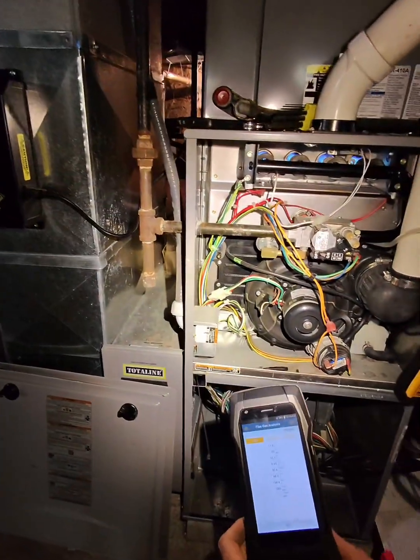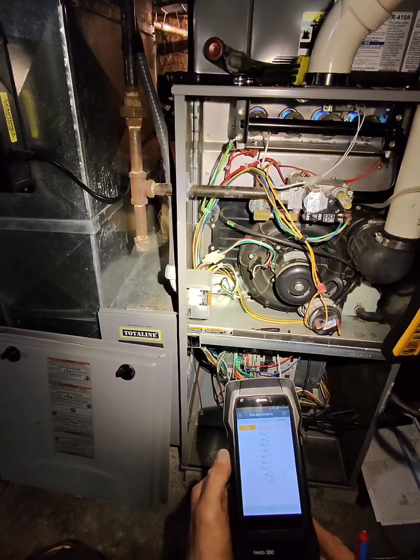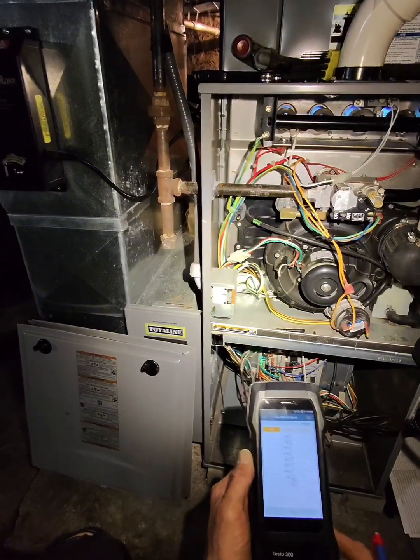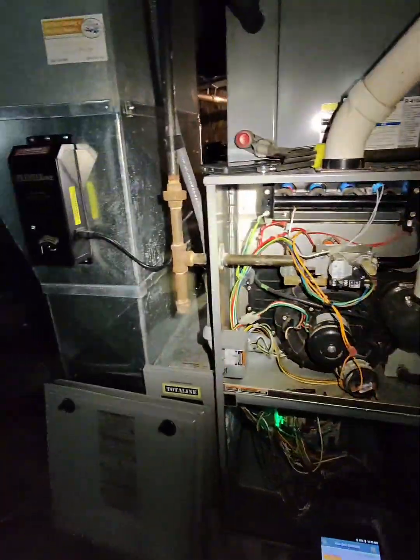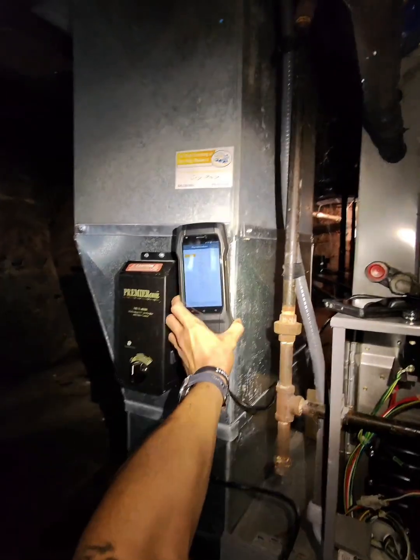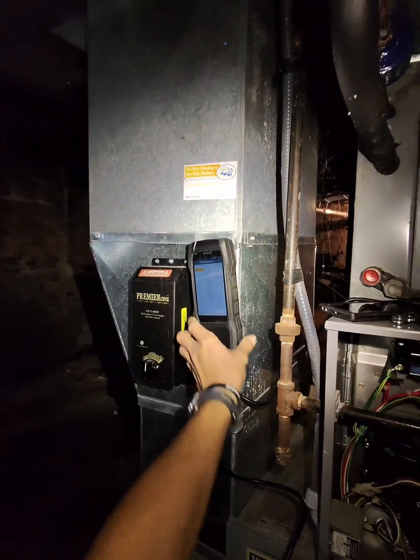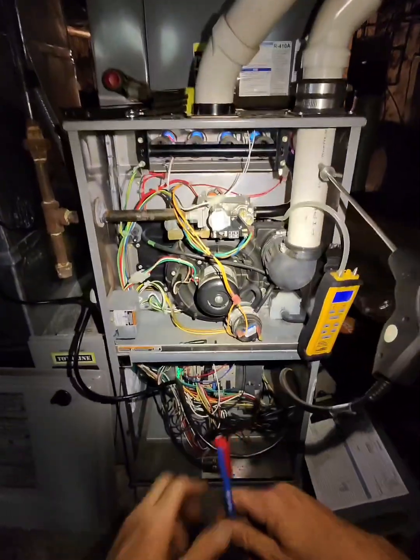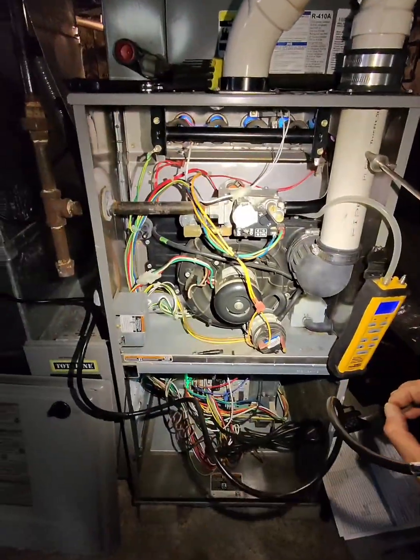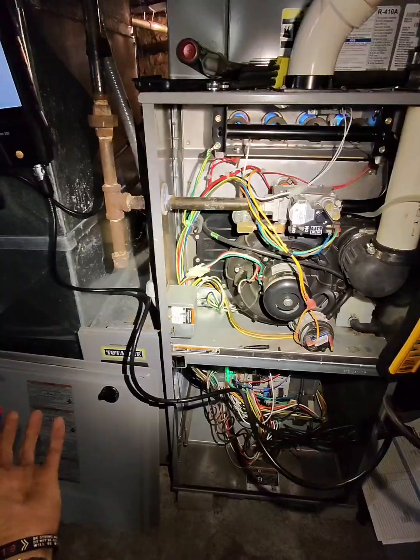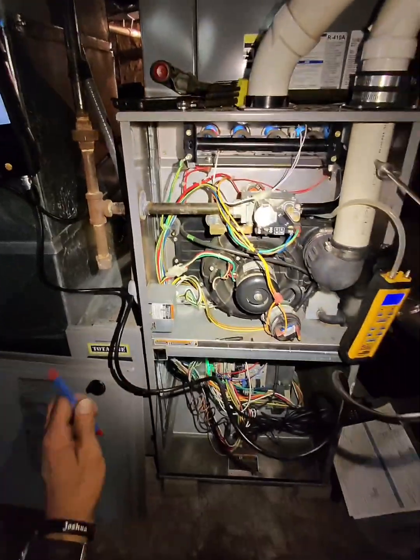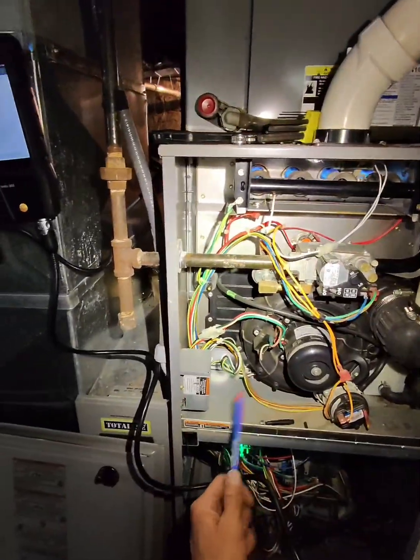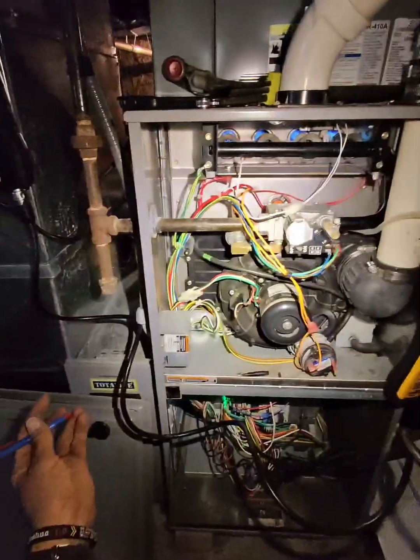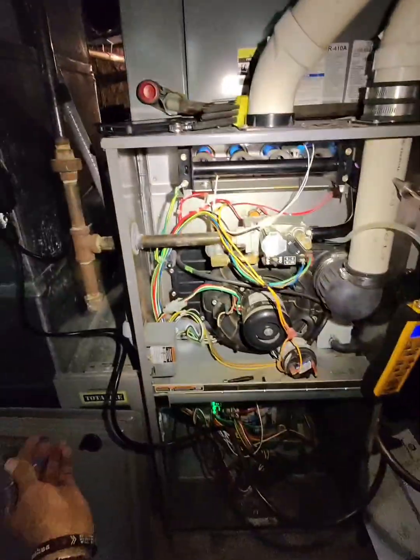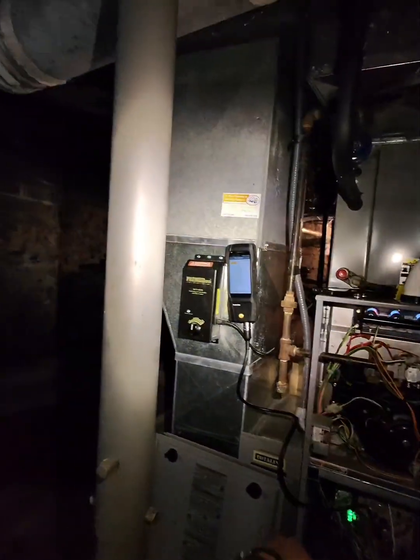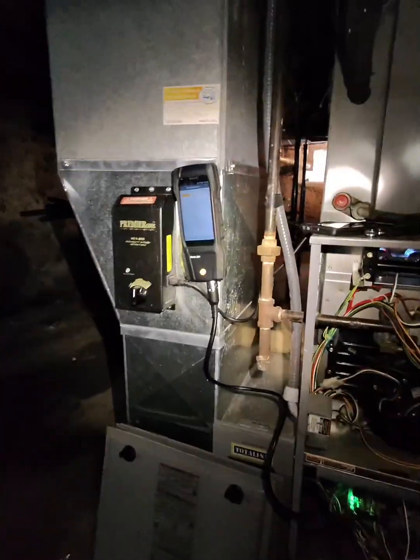Now, a lot of the times that excess air will be somewhere between maybe 50 and 120. So both of those are really high. And we've been finding, in the beginning with these furnaces, for the first maybe 10 years, Carrier thought that these heat exchangers were bulletproof, that they were never going to go bad, because it's a stainless steel secondary heat exchanger. So they thought that it was just never going to go bad.